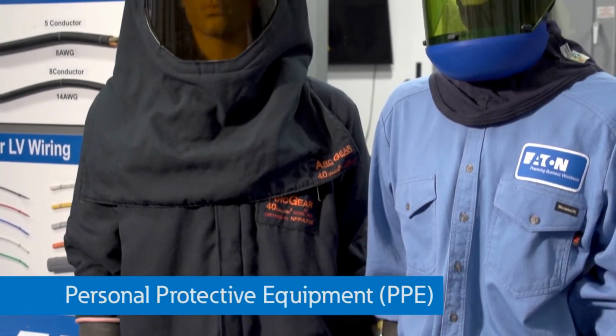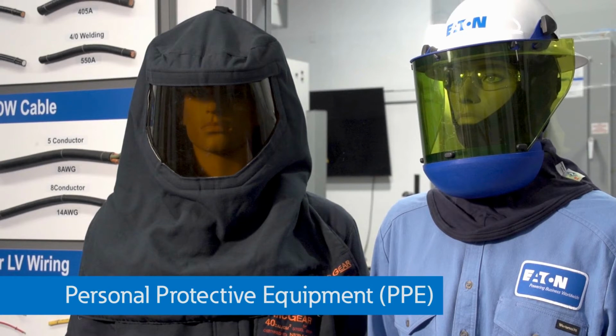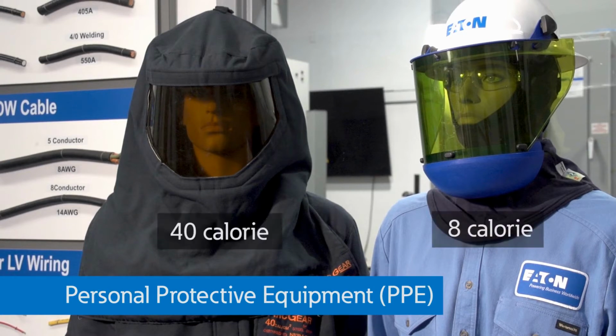The different calorie suits that you might have to wear, whether it's a 40 calorie suit or even a lower suit where you only need to wear just a face shield and a fire retardant jacket, compared to a 40 calorie where you have to wear a full suit head to toe, including a full hood. Personally, as a field electrician, I've always found it easier to work in a lower calorie suit. The higher the calorie suit, the more protection it gives you, but at the same time, that more protection also means you have more layers on top of you that you're not used to working in. The PPE that you wear to protect yourself depends on the incident energy and voltage level. These two arc flash suits are examples of an 8 calorie and 40 calorie system.